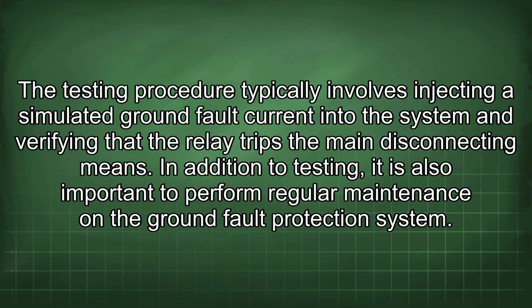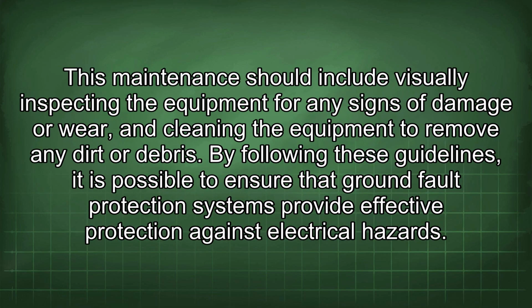The testing procedure typically involves injecting a simulated ground fault current into the system and verifying that the relay trips the main disconnecting means. In addition to testing, it is also important to perform regular maintenance on the ground fault protection system. This maintenance should include visually inspecting the equipment for any signs of damage or wear, and cleaning the equipment to remove any dirt or debris. By following these guidelines, it is possible to ensure that ground fault protection systems provide effective protection against electrical hazards.